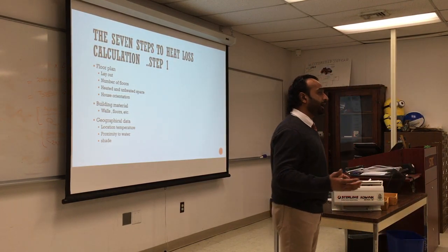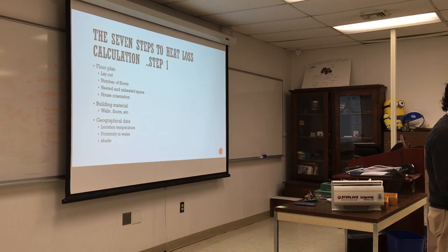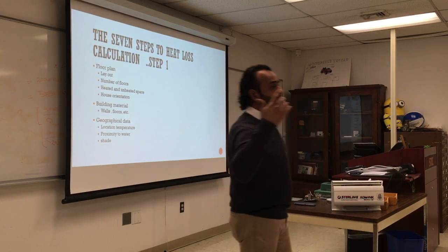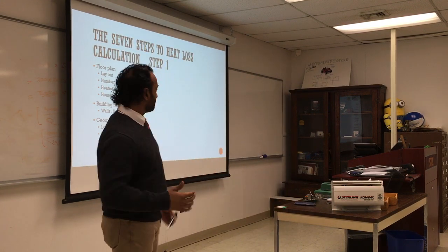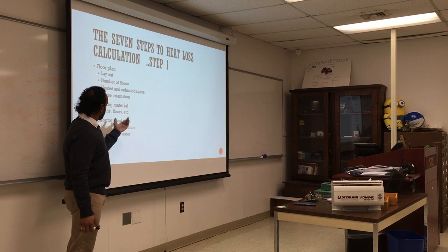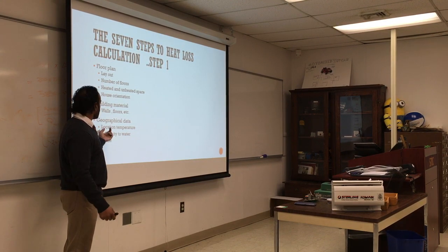But usually, hot air rises. That's why we like radiant floor. Radiant floor heating gives you a very warm floor, around 85, and around 65 within 5 or 6 feet. So that's more comfortable. So we're gonna look at walls, floors, and other materials, windows, inspect the windows.